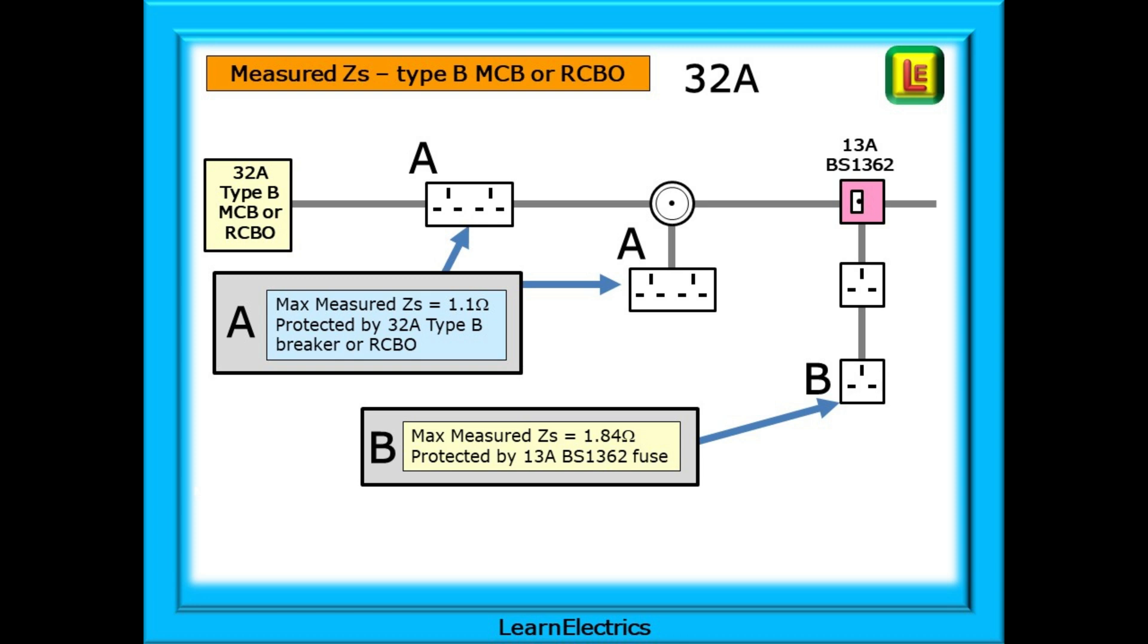However, at point B, we have two sockets that are protected by an FCU with the 13 amp BS 1362 fuse installed. The furthest socket on this spur will therefore have a maximum permissible measured ZS of 1.84 ohms. The 1.84 ohms for ZS only applies to the socket on the fused spur at point B.